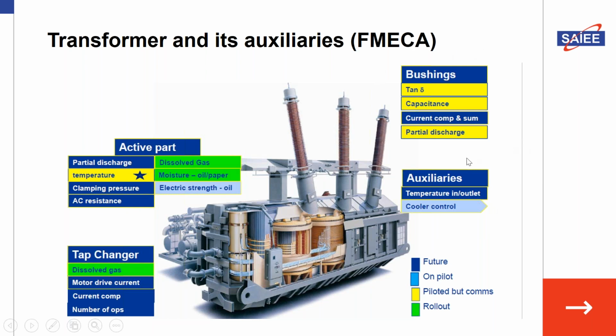For the bushing, which is really the receiver of the voltage and helps keep the insulation with the tank so you don't have flashover, this is a very important part of the accessories, and it also deteriorates on its own. So we measure it for its capacitive properties with a tan delta test as well. We also check that there are no partial discharges from sharp edges that could be compromising the insulation. So this is a bit of an analogy between the human body and what you could test for in your annual medical check, as well as what we regularly look for in one of our most strategic assets, which is a power transformer.